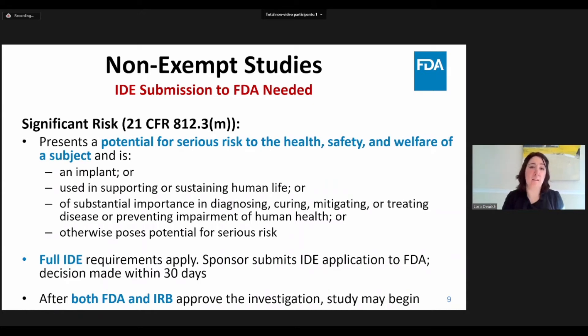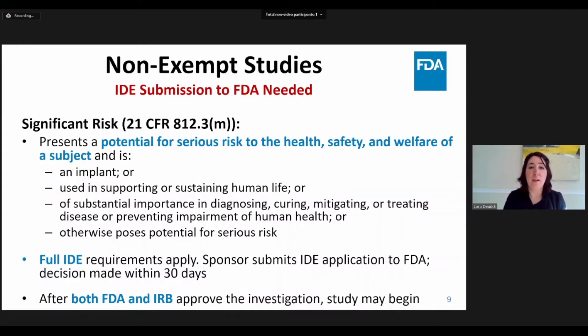A significant risk study, on the other hand, is one that presents a potential for serious risk to the health, safety, and welfare of a subject and meets one of the four criteria shown here. These studies are subject to the full IDE requirements. One possible example is when a device is used to influence a treatment or diagnosis of the subject. If the device is simply collecting information from the patient, then this may not be significant risk. However, if the collected information is then used to make decisions about the patient's diagnosis or treatment, then the study is likely significant risk.